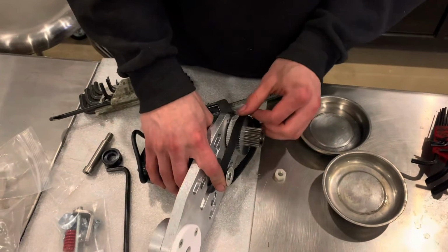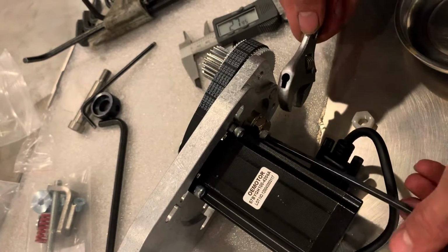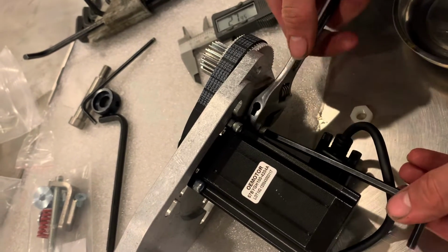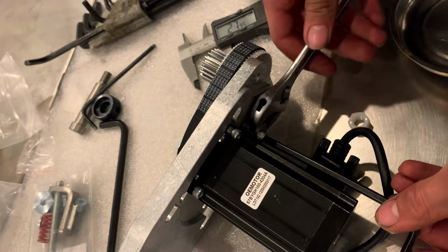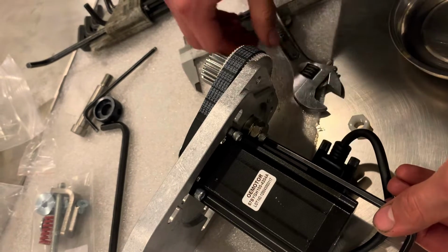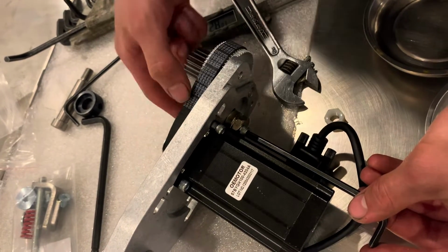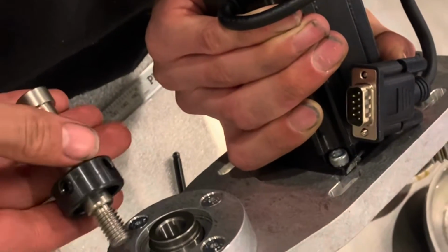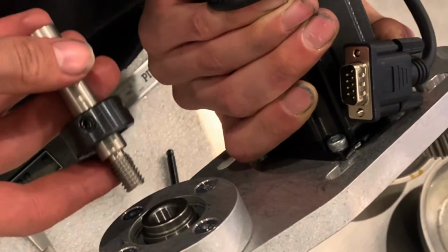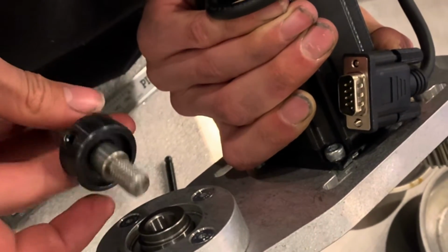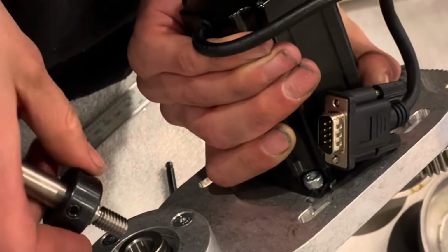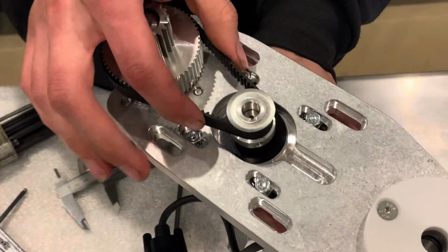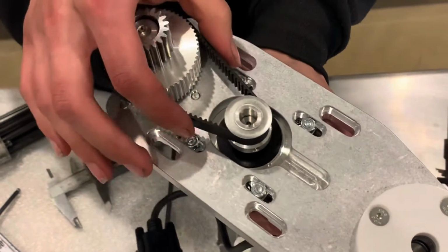The motor's loose, so you can put the belt on. You can keep that bolt loose while you put a wrench around the nut and turn it against the motor so that it tightens the belt. Put the swivel axle bolt and this eccentric collar in with the pocket facing the bearing. You want the belt to flex less than 1/8 of an inch.